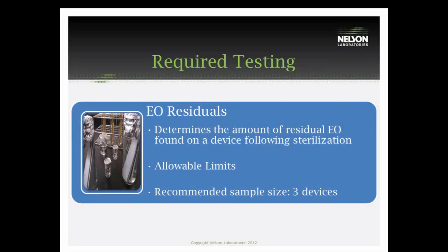Following the full cycle, we'll test the samples for EO residuals. These samples will have been exposed to both a half and full cycle. What this testing does is determine the amount of ethylene oxide residuals found on the device following sterilization. ISO 10993-7 states specific levels that these residuals need to be under to pass this test. We recommend three samples for this testing.